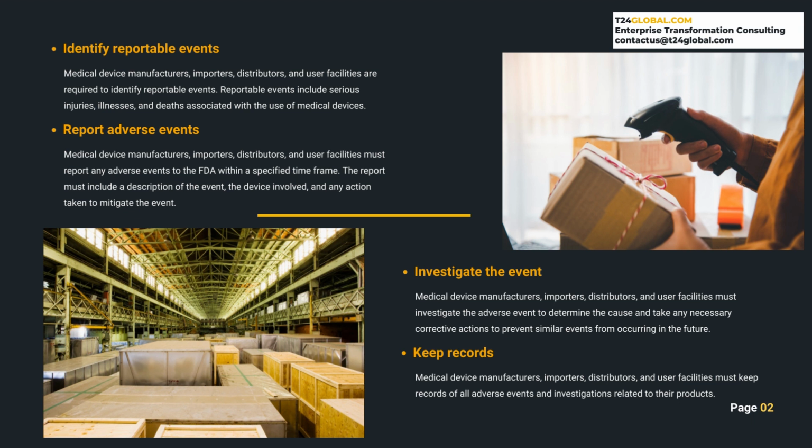2. Report adverse events. Medical device manufacturers, importers, distributors, and user facilities must report any adverse events to the FDA within a specified time frame. The report must include a description of the event, the device involved, and any action taken to mitigate the event.